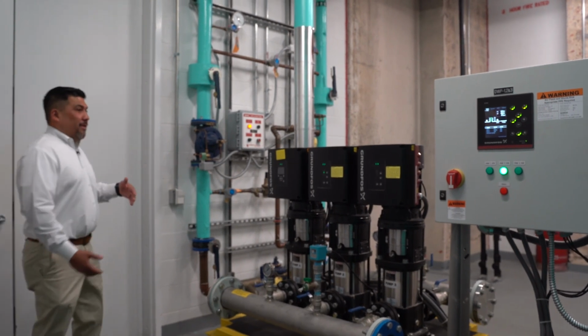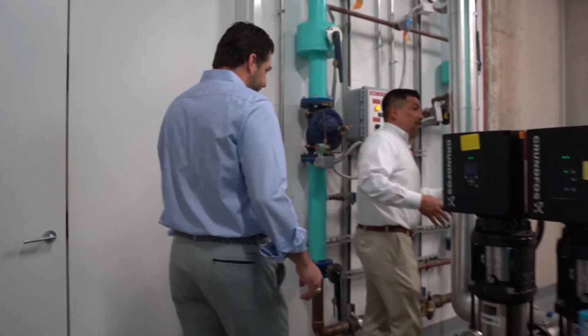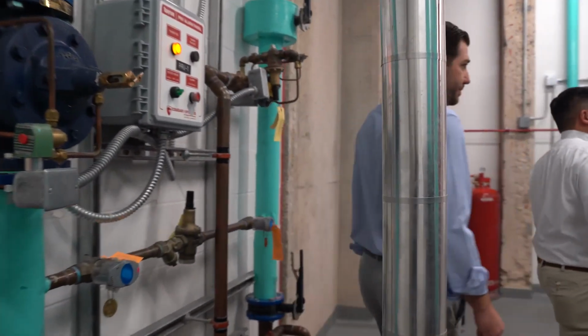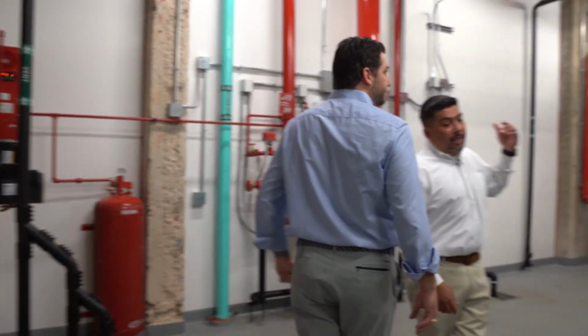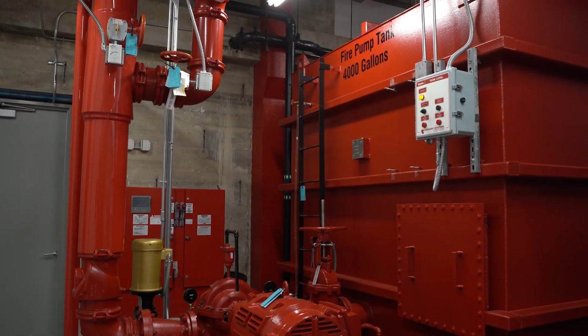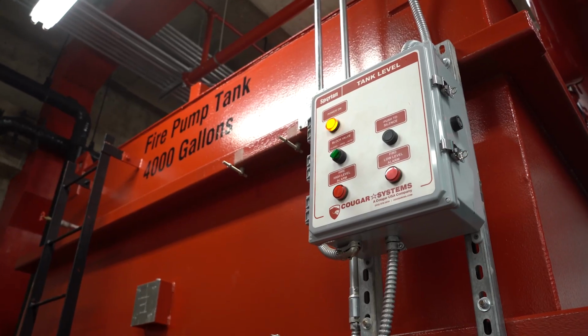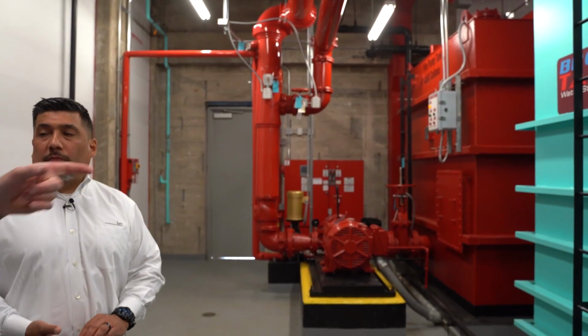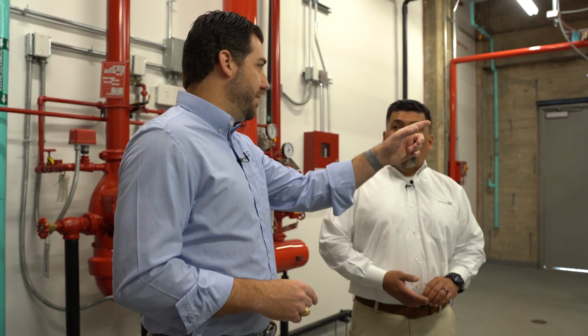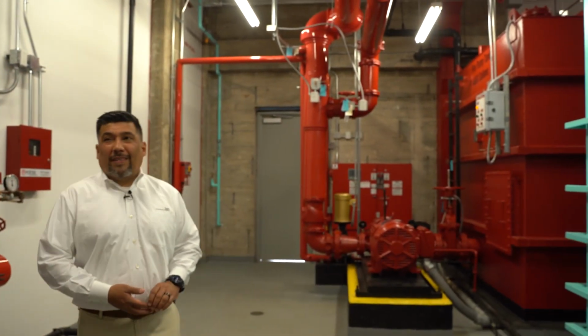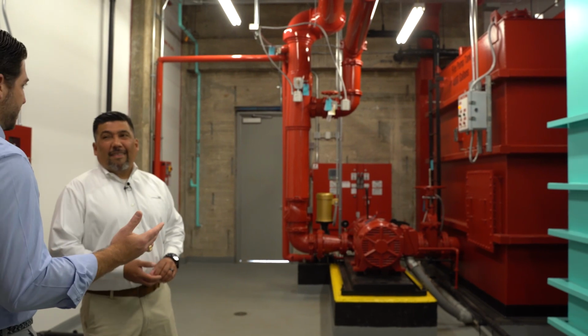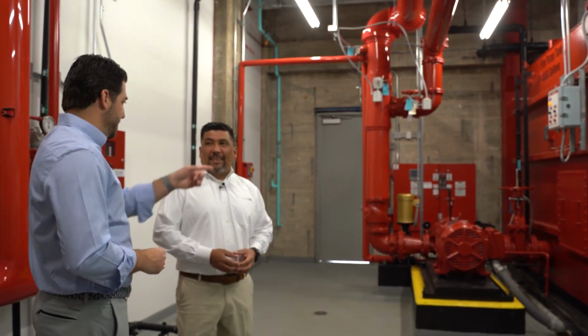The cool thing about this building is not a lot of buildings have two separate tanks - one for domestic water and one for fire water. It's a unique code in the city of Houston to require the house tank or break tank for the domestic side, so you have to have that air gap and backflow prevention for the booster pumps. That's specific to Houston - most people are used to seeing the fire tank with fire water storage for fire protection and the pump off of it. So it's definitely cool to have two separate tanks and two separate feeds.